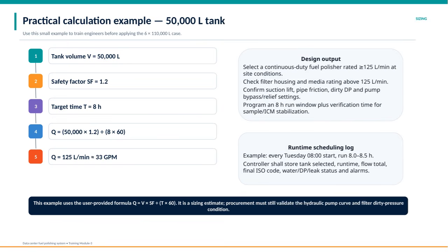It's important to verify that the filter housing and media are rated for this flow and to check pump parameters like suction lift, pipe friction, and differential pressure settings, including any bypass or relief valves. For runtime scheduling, an 8-hour run window is programmed, with some buffer time for sampling and instantaneous contamination monitoring stabilization. An example schedule could be running the system every Tuesday starting at 8 a.m. for 8 to 8.5 hours. The controller should record important parameters such as the selected tank, runtime, flow totals, final ISO cleanliness codes, water and differential pressure status, along with any alarms.